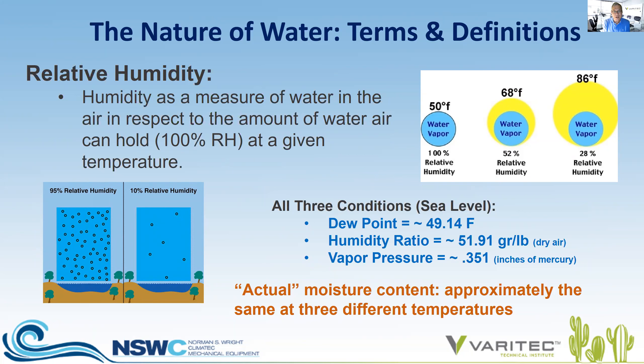Relative humidity is associated with temperature. The warmer the air, the more thermal energy in the air, the more moisture or water vapor can be held at a higher energy state. If you look at the chart, you can see that the actual dew point, humidity ratio, and water vapor at all three states remains the same, but the relative humidity changes because it is a percent of water in the air in relation to the amount of water the air can hold at that temperature. ASHRAE is moving away from relative humidity because it varies with room set point temperature, whereas dew point, humidity ratio, and vapor pressure will not change.